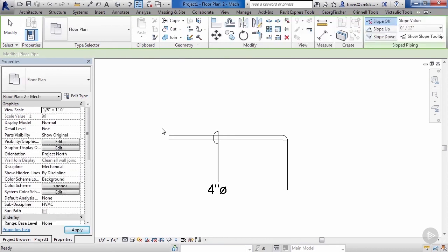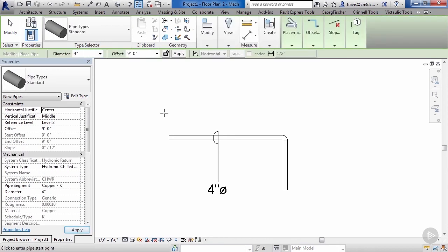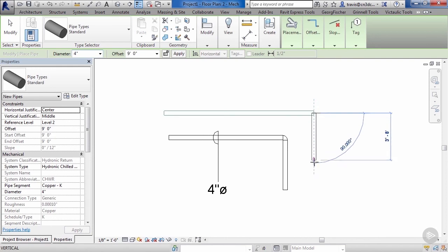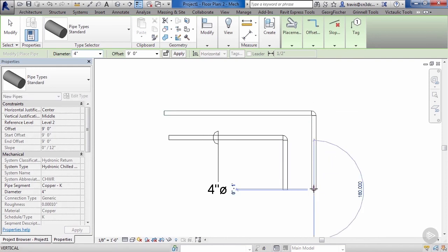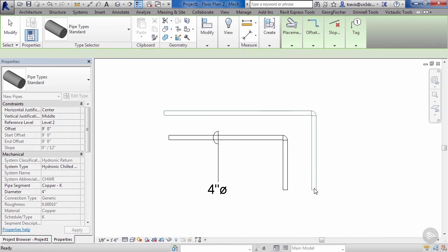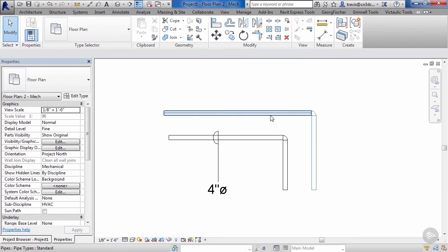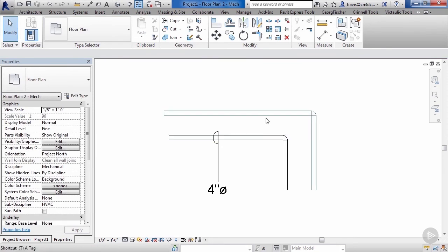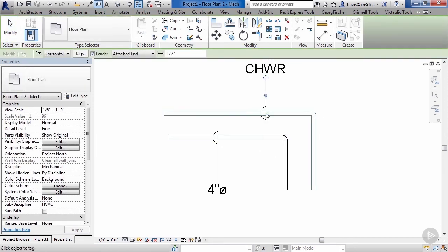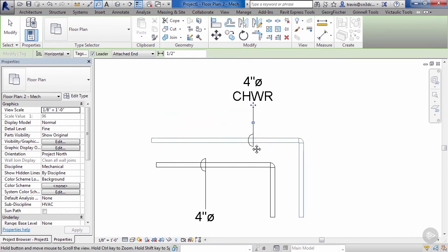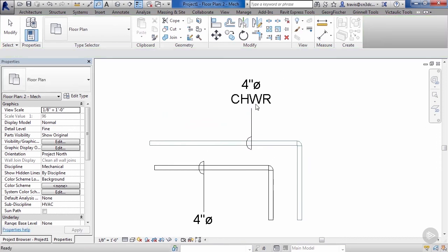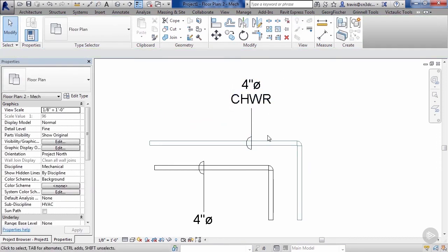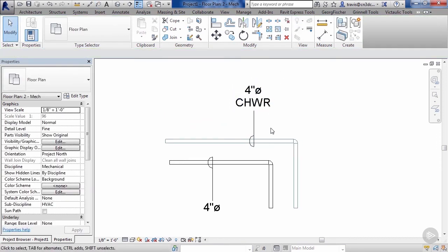Let's go ahead and we'll draw a new set of pipes. Type in PI and from our system type, let's go ahead and select our new hydronic piping system. As you can see, the color is different—that's easy for somebody that's working in the Revit file to see. And then when we go ahead and we tag it, we can see we now have a new four inch diameter chilled water return.